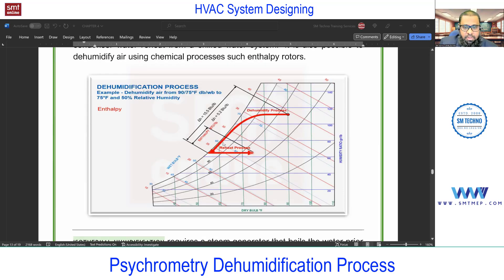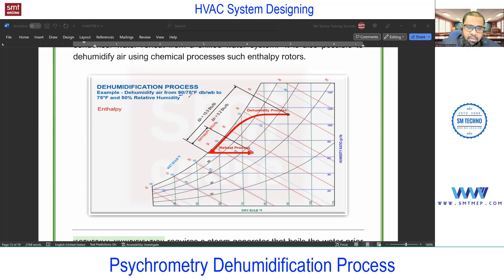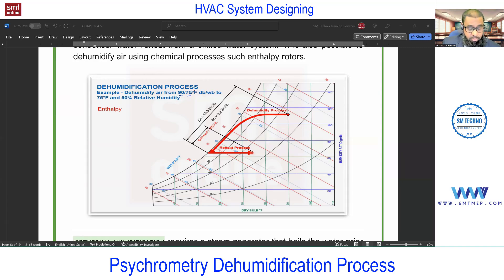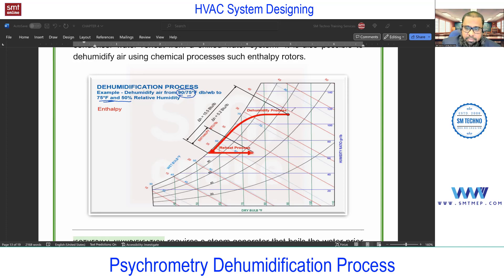Let me zoom in. The different conditions and points: the initial condition is 90°F dry bulb and 75°F wet bulb — this is the room air initial condition. The required condition to maintain is 75°F dry bulb at 50% RH. So this is the present condition (point 1) and these are the required conditions (point 2).